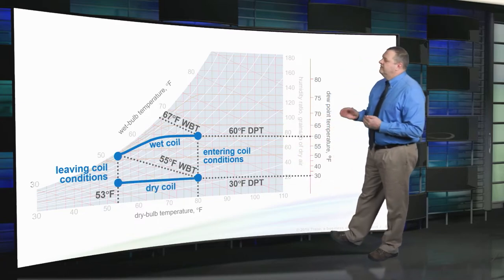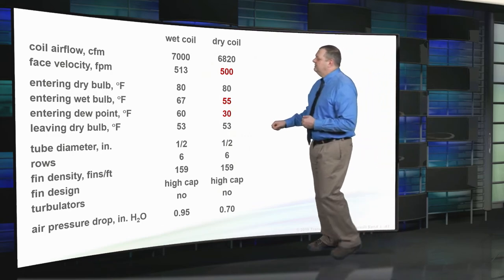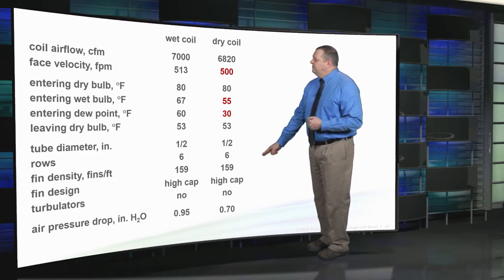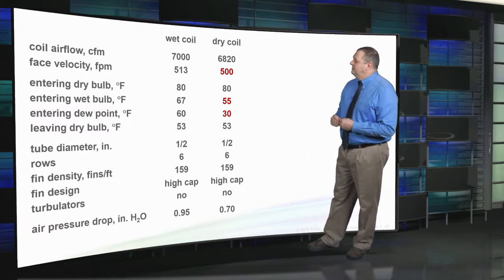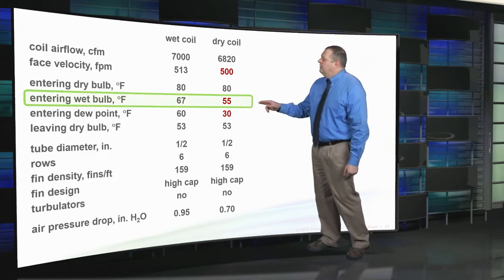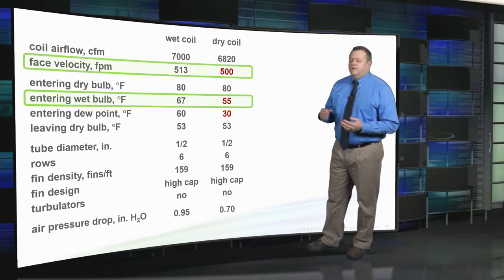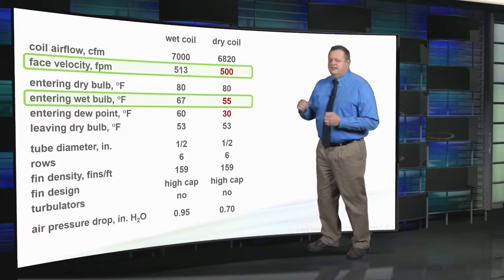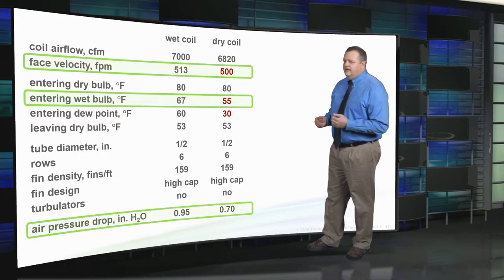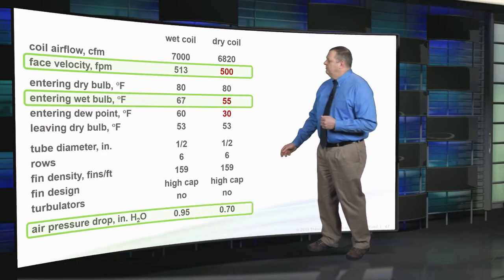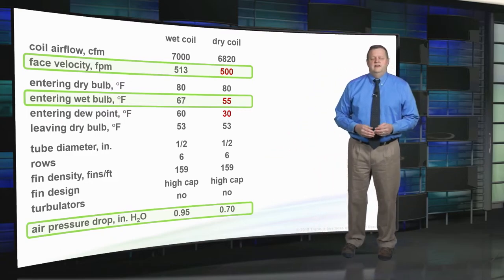To check if a selected coil complies with the ASHRAE 62.1 air pressure drop requirement, use the manufacturer's selection software and rerun the performance of the selected coil with air conditions that will cause the coil to run dry. In this case, by lowering the entering air wet bulb from 67 down to 55 degrees, the entering dew point drops to 30 — well below the coil's surface temperature — so the coil operates dry with no condensation. A 6-row coil from the previous example shows 0.95 inches pressure drop wet. Running it dry at exactly 500 feet per minute, the air pressure drop is 0.70 inches, which complies with the Standard 62.1 limit.